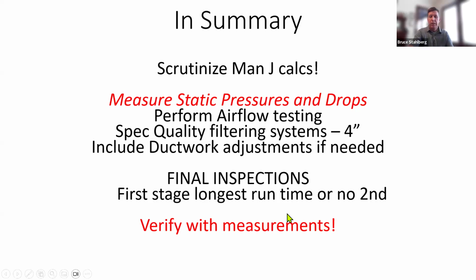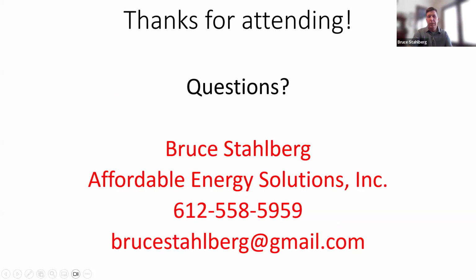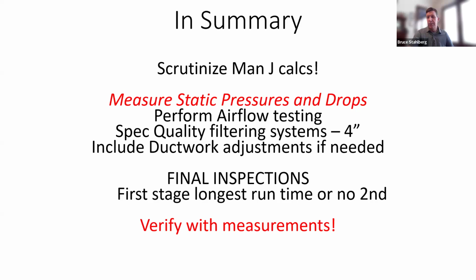And just verify the installations. So we are required under weatherization, DOE and the State Department of Commerce to do temperature rise. That's actually a pretty weak test. There's probably 5 or 6 different reasons why that isn't as accurate or as good of a test as static pressures is.